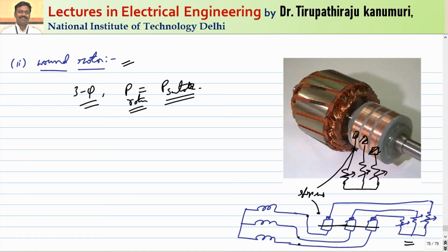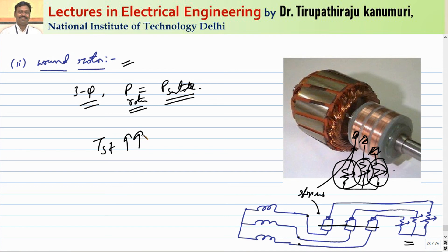By controlling the value of the external resistance connected via brushes and slip rings, we can control both torque and speed. For applications requiring high starting torque, variable torque, or variable speed, we go for the slip ring induction motor. However, the problem with the slip ring induction motor is that because there is a winding, there is a chance it will get damaged, so maintenance cost is more compared to the squirrel cage motor. The starting torque is more in this case because the rotor resistance R2 is higher.